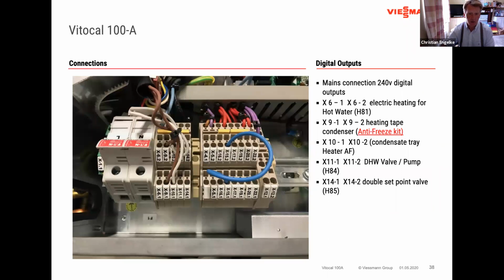The electrical connections are located on the top of the machines, so again, easily accessible for the electricians and easily labeled. It just needs the power supply and the connections to the 3-port valve, which is located inside the property, and the hot water sensor. All the other cables are already fitted into the machine, factory fitted.